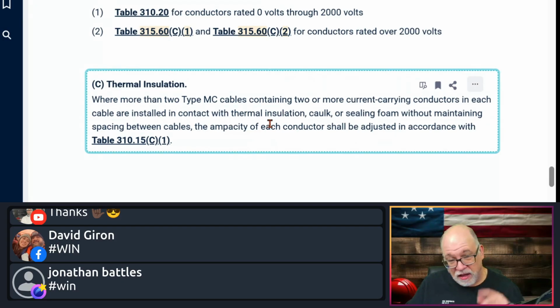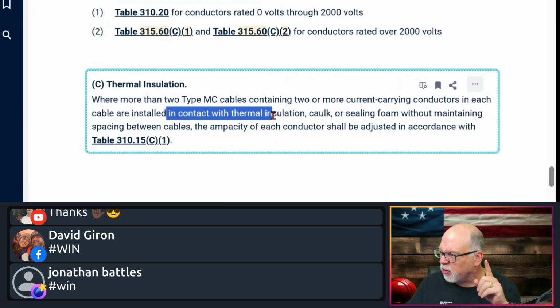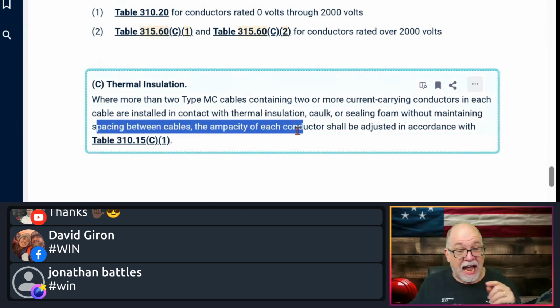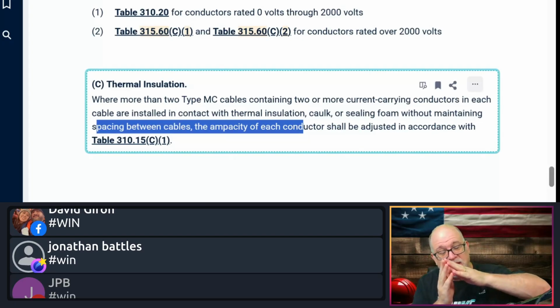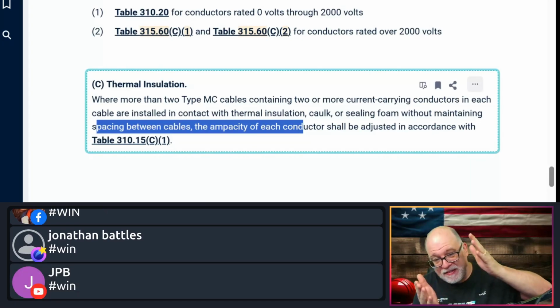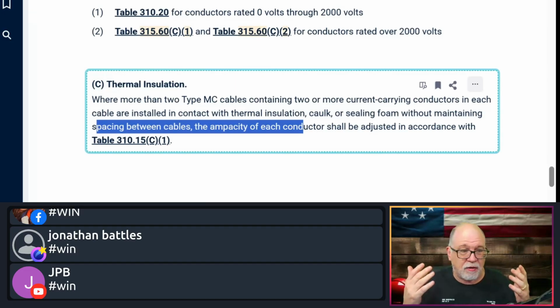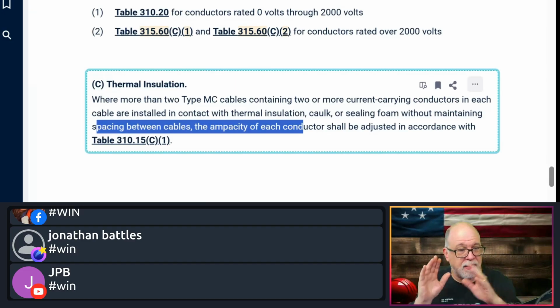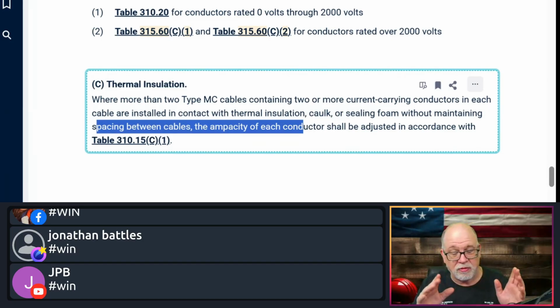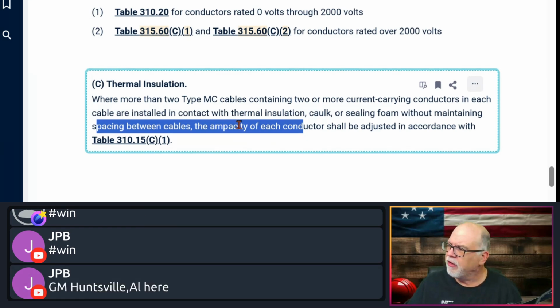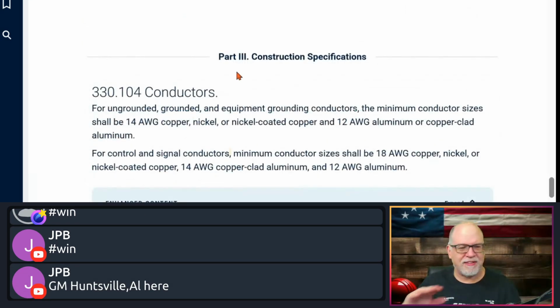Okay. So again, read it. It says are installed in contact with thermal insulation, caulk, or sealing foam without maintaining spacing between the cables as they go through that caulk, that sealing foam, or that thermal insulation. Now, if they come in contact with thermal insulation and they're not touching, right? They maintain spacing through that contact area, then I don't have to worry about 310.15(C) at that point, based on this issue. Got other issues, but not in this issue. So it's also important to read the details. You know what I'm saying? Details matter. Now, lastly, we'll talk construction. Again, this gets taken care of by the manufacturer. You don't have to lose brain cells over this, okay?